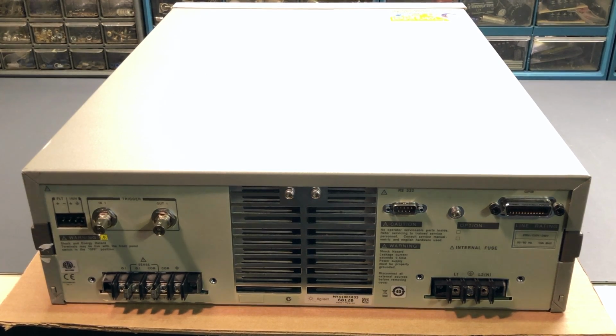Now something else that I noticed is that the factory applied sticker right here says that this instrument is set for a 220 to 240 volt AC input power, but this instrument can be set for 120 volts, and that's actually what I want it to be set to for my purposes. So once the top cover is removed and we're looking around inside, we'll take a look at the voltage changeover connections, and I'll show you exactly what's involved with switching the voltage. Now, I don't know, maybe this instrument has already been set to 120 volts. There's no markings on the back that would indicate that, but it looks like it left the factory with the 220 to 240 volt range already set up. So we'll take a closer look at all that once we're inside the instrument.